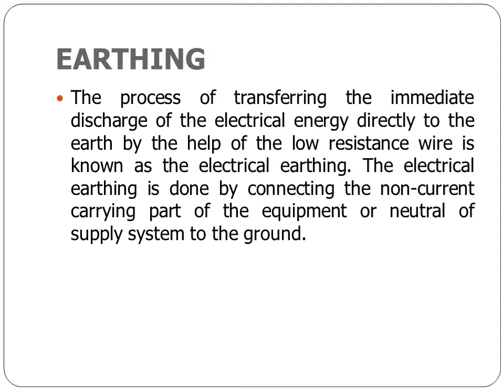The definition of earthing: the process of transferring the immediate discharge of electrical energy directly to the earth with the help of a low resistance wire is known as electrical earthing. Electrical earthing is done by connecting the non-current carrying part of the equipment or the neutral of the supply system to the ground.